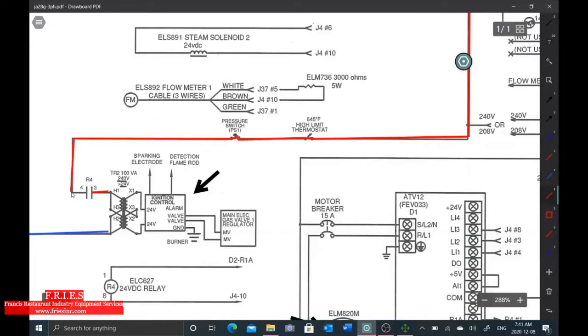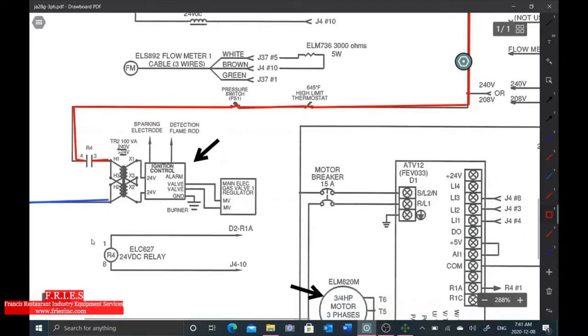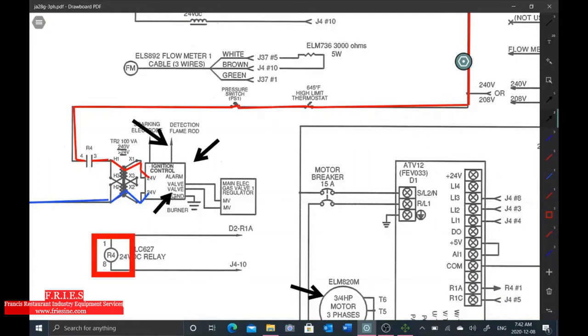From there we feed pin 4 on this R4 relay. The contacts are normally open. Okay, what closes the contacts is this coil here, which basically goes back to the board. That's your call for heat. Okay, once our transformer's hot, we get our 24 volts to our module. Okay, once we have our 24 volts to our module, we're going to start our spark sequence and flame detection. And if we have good flame detection, 24 volts will stay on the gas valve terminals for the module, and we will get our power to our gas valve, and that would be completing the circuit.